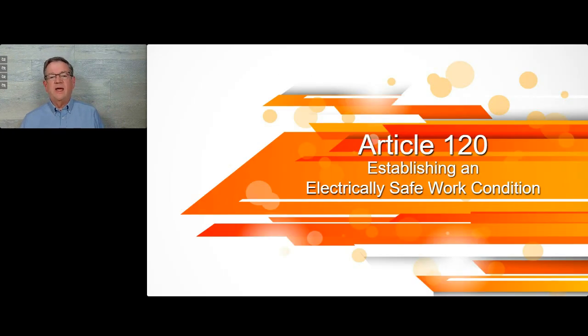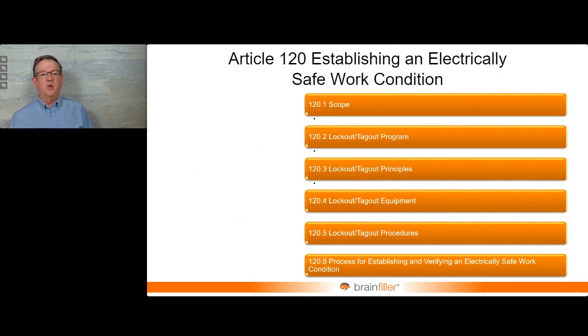Article 120, establishing an electrically safe work condition. So 110 defines the general requirements. 120 is really at the heart of this: establish an electrically safe work condition, make the system safe. And there were a few changes here as well. The first change was just reorganization. Because we have a new scope, that meant everything else was going to be renumbered within here.